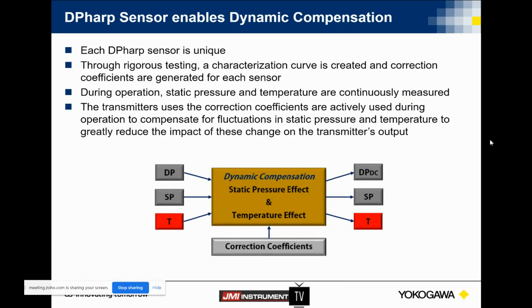So dynamically compensated in the fact that we can have not just our DP reading, but also our static pressure and temperature reading. These transmitters are characterized down in Newnan, Georgia, and this characterization curve is put into the transmitter itself. So if we're seeing any changes on the static pressure or the temperature of that capsule, we're dynamically compensating for those changes in process condition and giving you a nice, tight, accurate reading. So you don't have to go out and zero if all of a sudden your line pressure happens to be a little bit different than the transmitter was originally set up for.